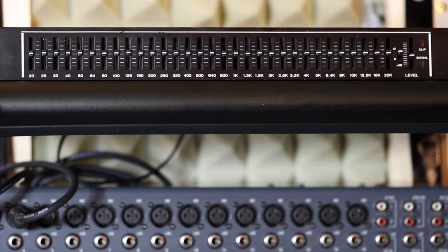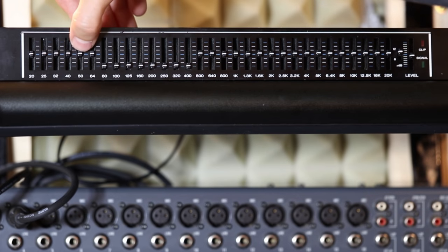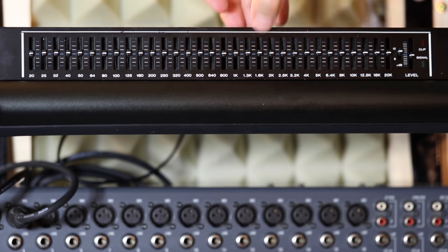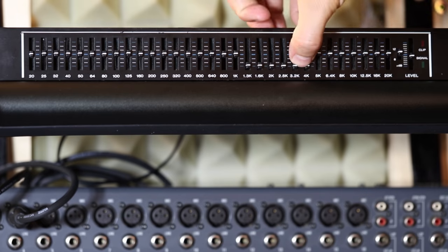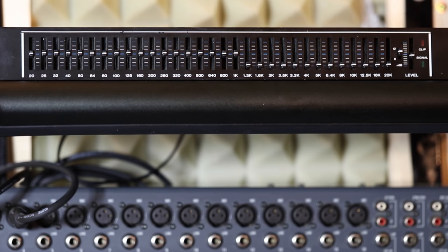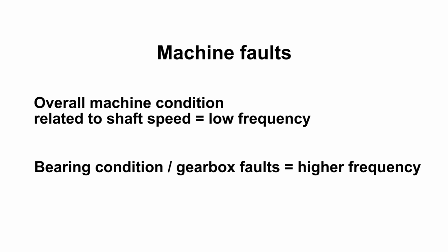Talking about the speaker again, can you separate each noise which comes from the speaker while playing some music? You can easily separate the bass, low frequencies, from treble or high frequencies with an equalizer. Why are we still talking about speakers? Because it is very similar to the vibrations on the machine. On the machine, we also want to separate these bass and treble noises, but here we are talking about separating machine faults, such as overall machine condition related to shaft speed, low frequency, and bearing or gearbox faults, higher frequency.